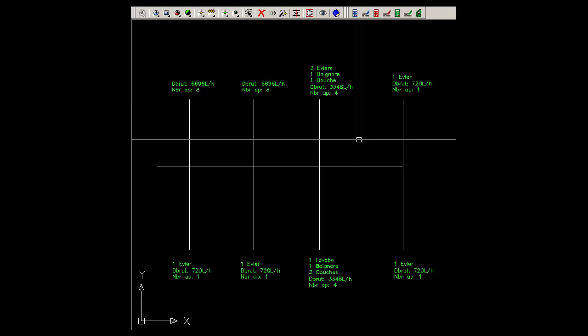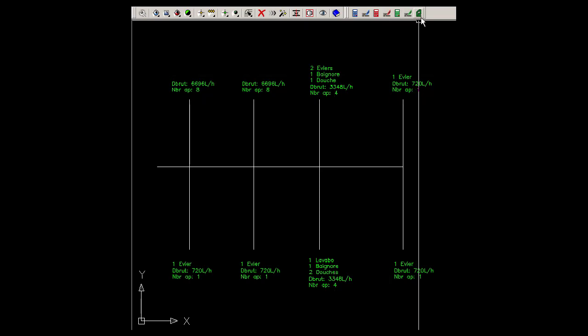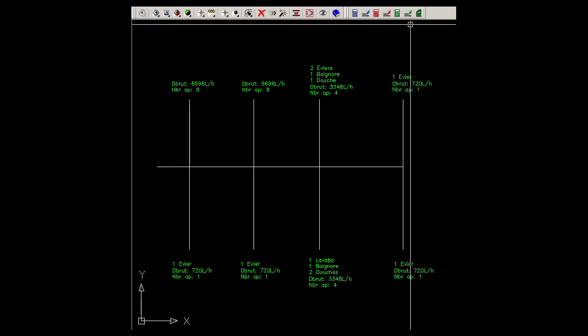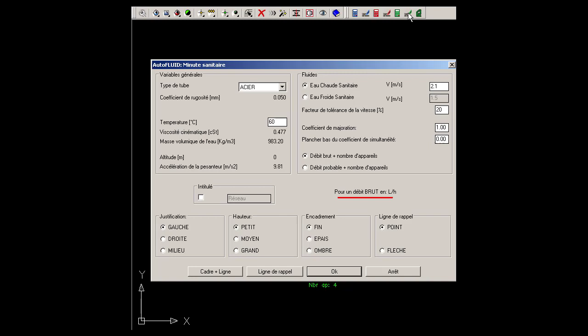Once the skeleton of the network is drafted with the line command in AutoCAD, and once the value of each flow is inserted using the command computation of typical flows in Autofluid, you can use the sanitary computation worksheet command to set the network sizes.